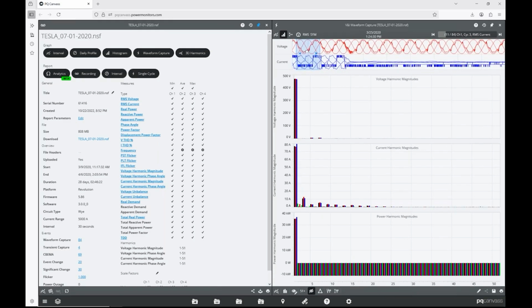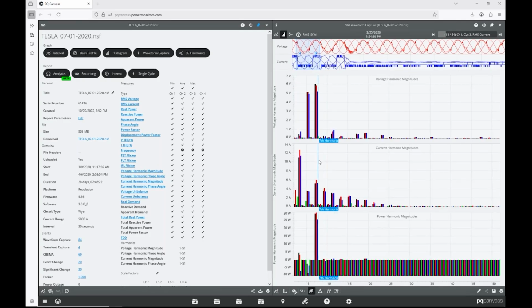Let's look at the harmonic distortion at the beginning. We see on the voltage a fairly prominent 5th and 7th harmonic. We also see on the current 5th and 7th harmonic. We also see some 3rd harmonic current, which is not typical for 3-phase harmonic loads, but with a bit of voltage imbalance, you will see that.